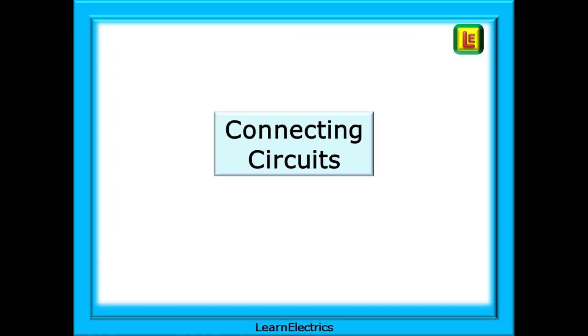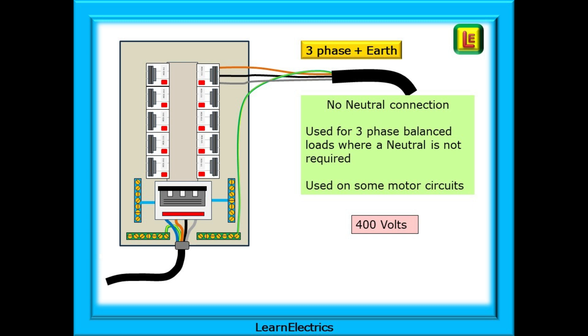Let's now connect some circuits to the board. Following a logical method, it's really very easy. And looking at an already wired board is just as easy once you understand the basics of the board wiring. We can begin with a three-phase plus earth circuit, a four-wire circuit. There is no neutral connection to this circuit and it is used for three-phase balanced loads where a neutral is not required.